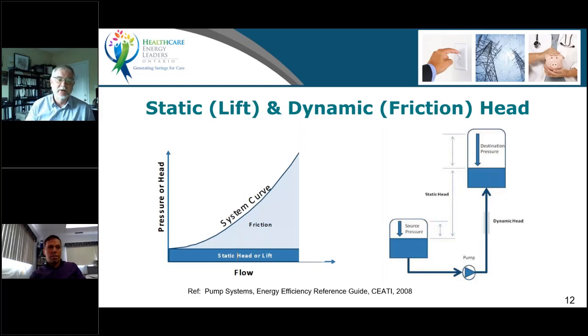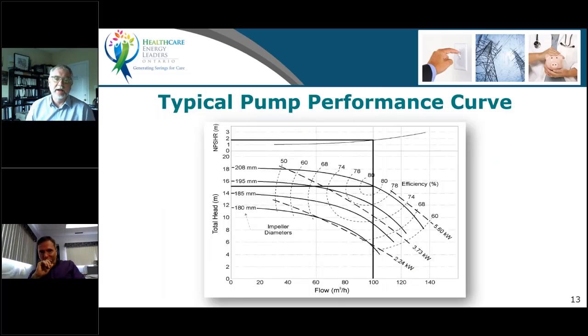Absolutely. So we need speed in a pump to generate pressure in order to move water through a static head or lift. But if it's a closed system, that doesn't apply. So for any given device like a pump, there is a relationship between head or pressure and flow. And typically we'll have pump curves, and on those pump curves we might have one line, which is the only curve for this pump. But you know what? There are four lines on this pump.